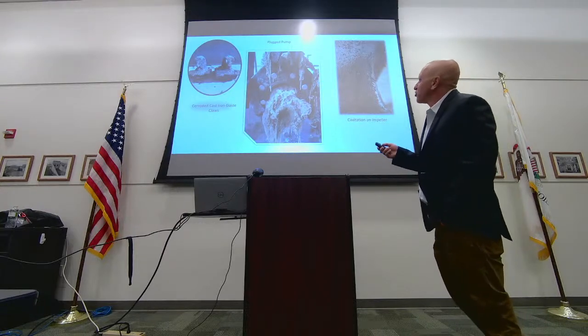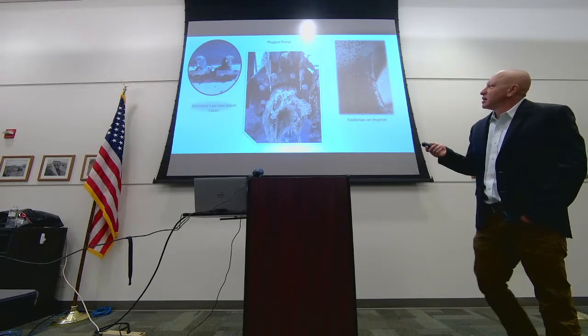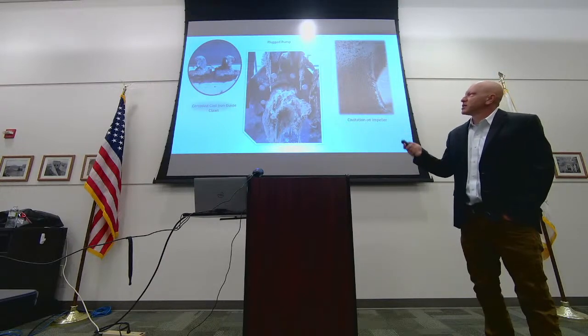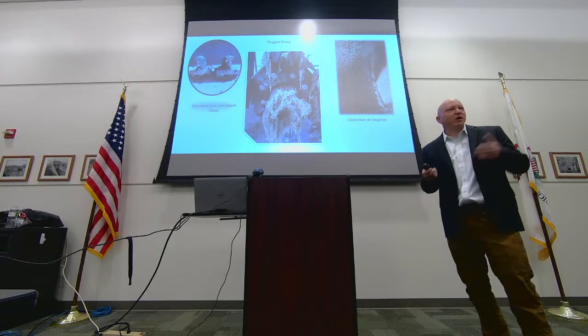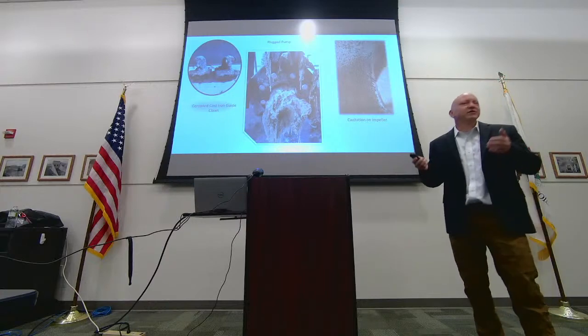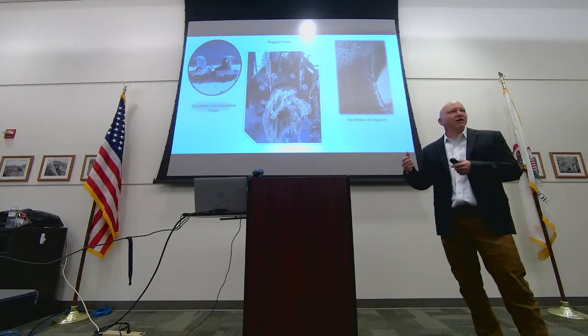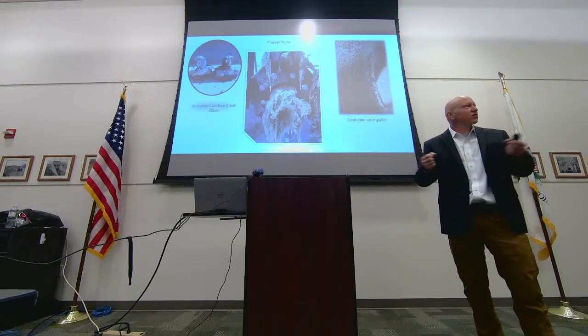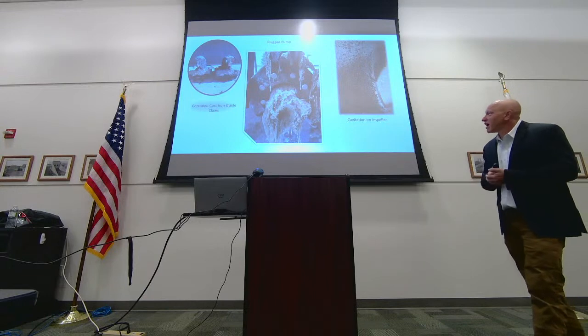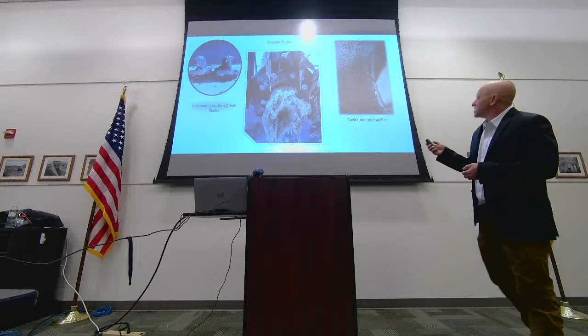So, pretty common troubles we see. The corroded cast iron. When we go out to look at something like that, it's not that I go to do a cast iron inspection. Somebody calls me and says, hey, I'm getting some weird noises, or my flow rate's down. And it turns out that there's a lot more vibration, and you were getting blow-by on the discharge elbow because things aren't seated right, or they're not staying seated right. They'll start off okay, and then they move. And of course, the clogging, that's pretty self-explanatory. We'll get into that in more detail. And cavitation on the impeller.